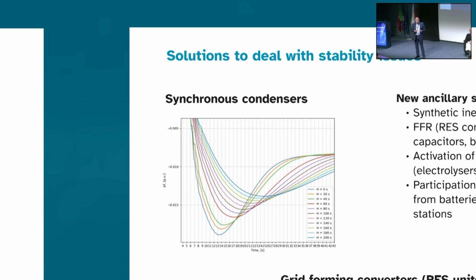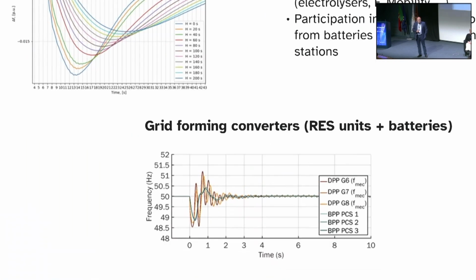These synchronous condensers could be thermal units that are being decommissioned and revamped, together with a flywheel on the shafts, used to provide inertia through the system. This way we get much better behavior from the system.